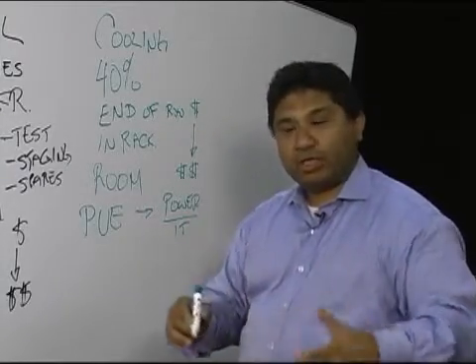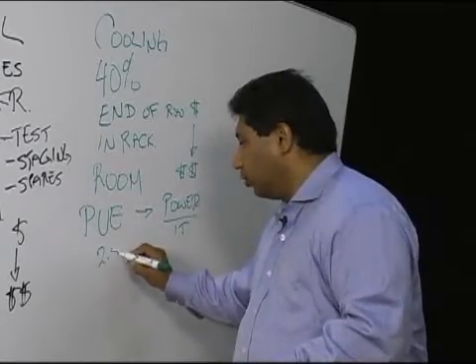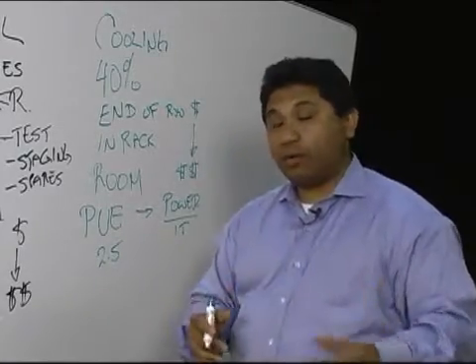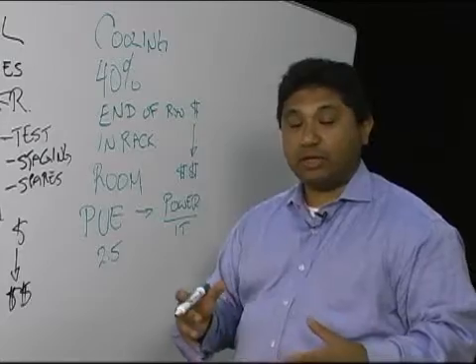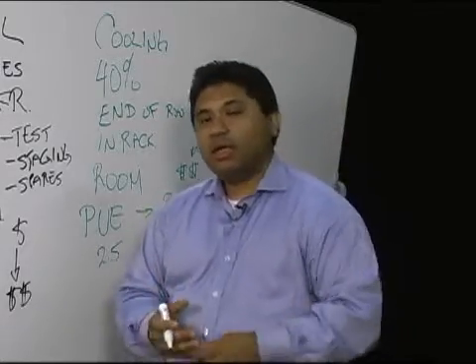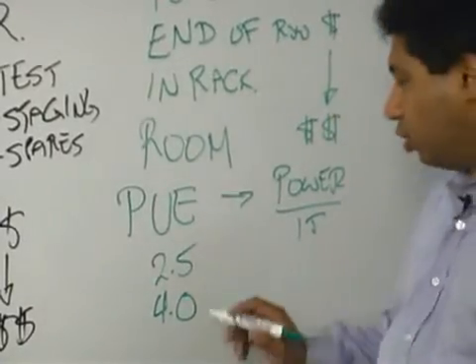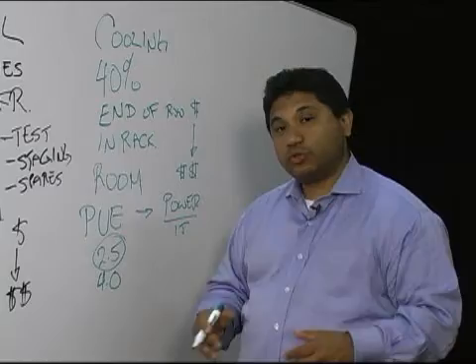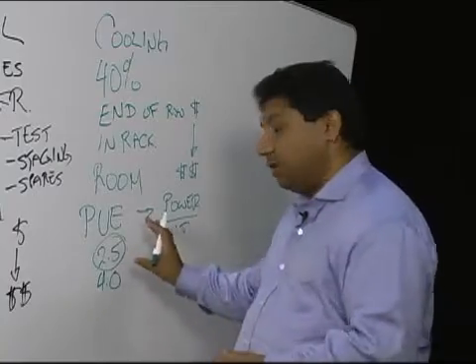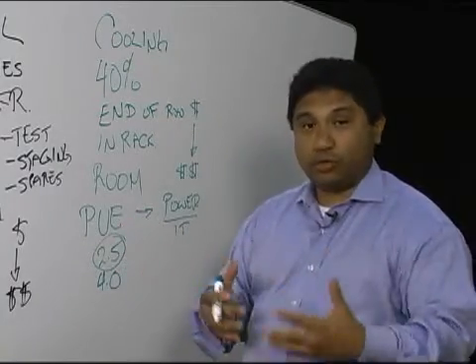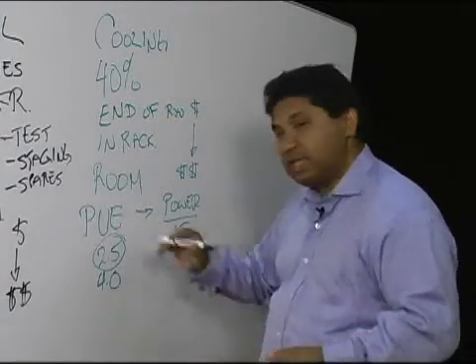A typical average data center is about 2.5. A very well-run one is about one, that's hard to get down to. You need a room that's specifically designed with power in mind. A poorly designed one is about four. So you want to try and be in this 2.5 range when you do your measurements. If you get a little bit above that, you want to take a look at maybe doing some things differently. But try and stay in that range.